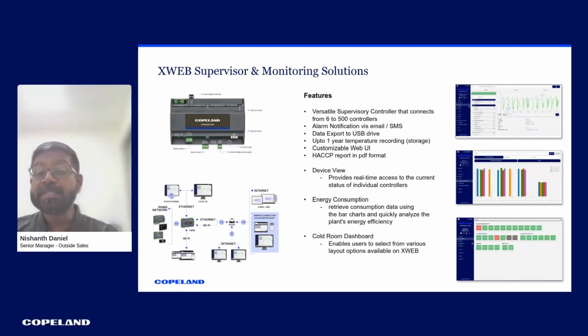These are also very versatile supervisory controllers, which can connect from a small capacity of around 6 controllers to a maximum of 500 controllers, which means that a customer or a contractor who wants to set up a remote operation center for a particular customer, a big customer like Amazon or Flipkart, can also use these kinds of solutions to have a single point of operation and remote operation and monitoring capability. It supports alarm notifications through SMS, and it has a user interface which is highly customizable.